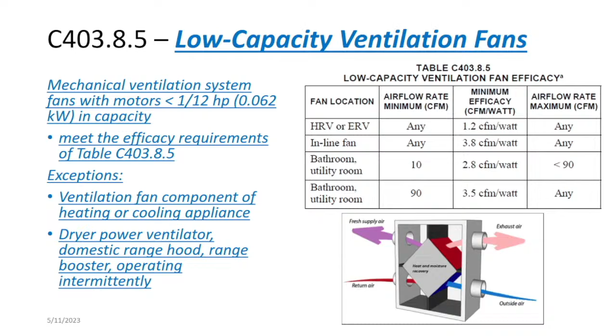Okay, there we go. A better view of a heat recovery ventilator down there, or energy recovery ventilator. The air going through this direction does not mix at all with the air going this direction. A good way I can describe this is sometimes this heat exchanger in here kind of looks like plastic cardboard, where you have all the little passages run through it, and you cut a bunch of squares and you stack them on top of each other, rotating each one 90 degrees to the other one. And guess what? Every other one, the air will go through this way, and the other ones will go through this way. So the air doesn't mix, but we have the ability to pick up heat and transfer heat based on the temperature difference between the two air streams.